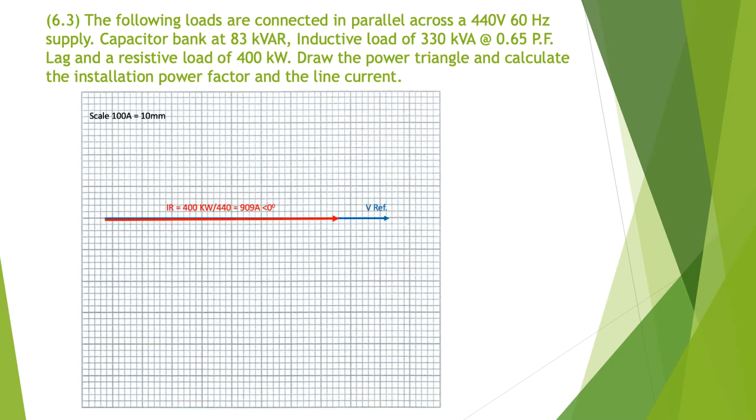So bottom of our power triangle we know that the wattage is in phase with the voltage so it's on the horizontal. We get IR equal to 400 kilowatts divided by 440, so we got 909 amps at zero degrees for our first current. For the resistive component that's the watts. Then we have a current so 83 kVAR divided by 440 and that is going to give us 189 amps at 90 degrees.